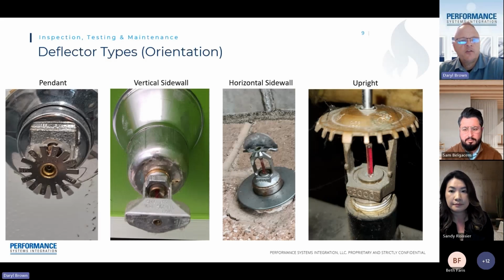Next, we have a basic breakdown of fire sprinkler heads. They are put together and developed based on where they're going to be positioned. On the left-hand side, you see a pendant style, which, if you look up and you have fire sprinklers in your office or location, is the basic style you'll see coming out of the ceiling. On the far right, these are called uprights. These are usually in attic spaces. You usually do not see these. Sometimes you may see them high up in a commercial building that has a high ceiling.